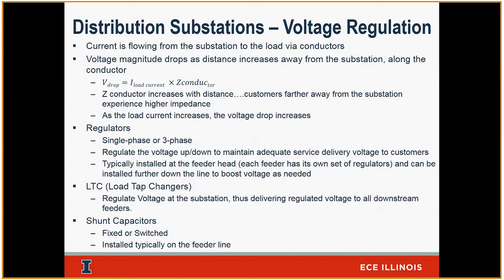That means any device that you've got is supposed to operate within this band. If the voltage dips below this band, your equipment is going to see abnormal behavior. It's going to dip in performance. Your lights might flicker. Your TV might not be as bright. Depending on what you've got, your equipment is going to behave in a non-satisfactory way, let's call it. So we, as a utility, try to make sure that the voltage coming out of your outlet is between 114 and 127 per code, okay?